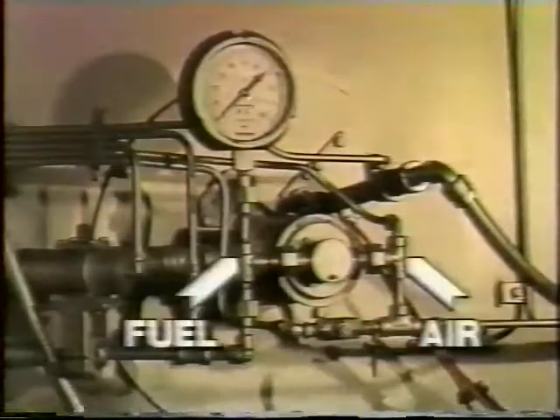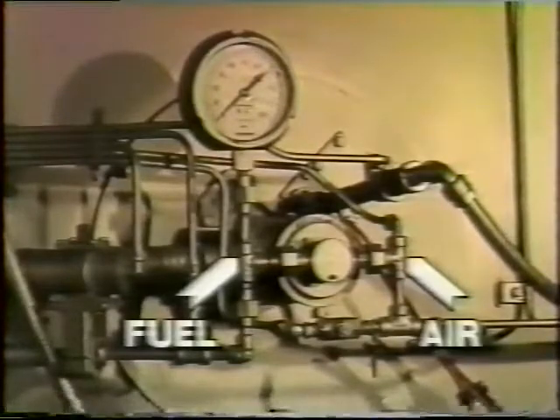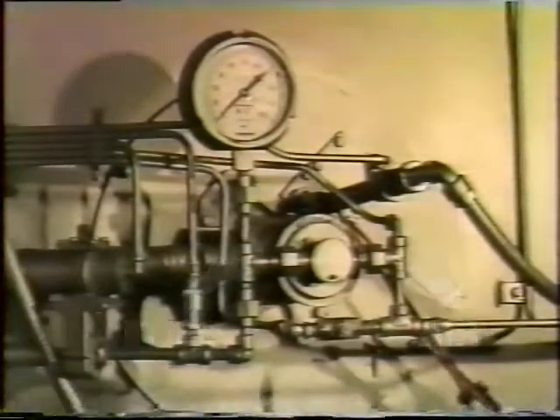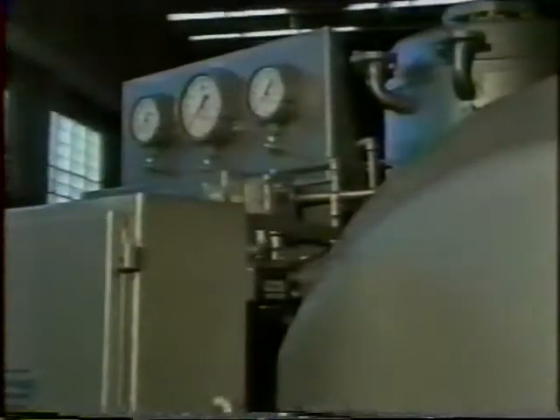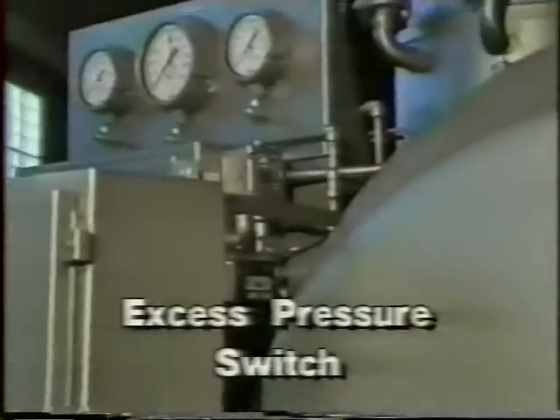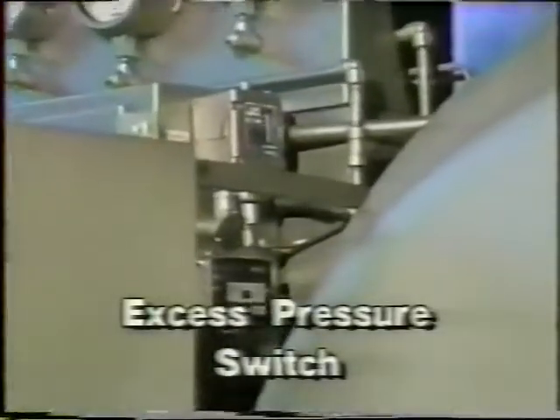This increases or decreases combustion air and fuel to the burner head according to the steam demand. An excess pressure switch with normally closed contacts in series with the burner circuit is installed in the steam sensing line. In case of excess steam pressure, the switch contacts open, cutting off the burner.